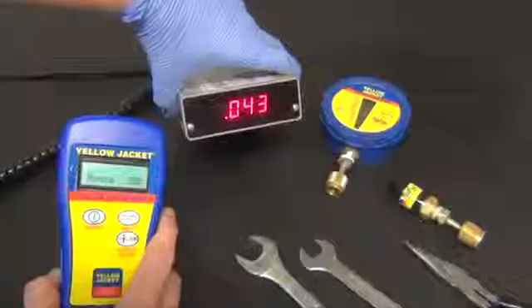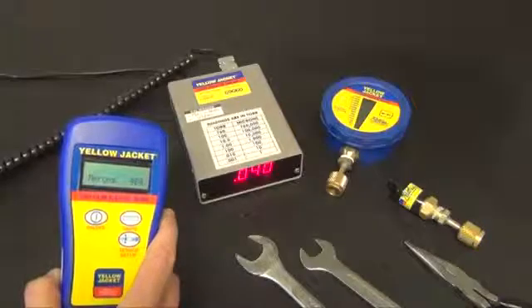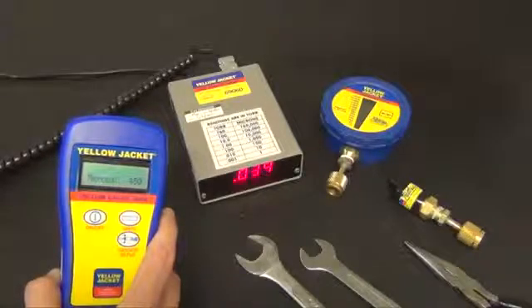As you can see, our test gauge is easily under 50 microns, whereas our contaminated gauge is still in the 400s.